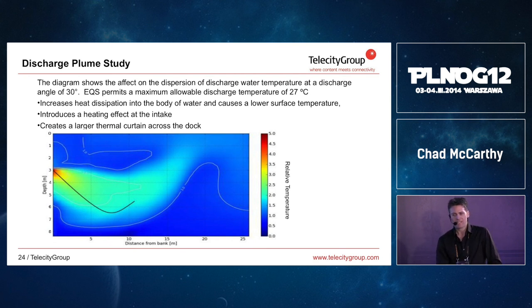This causes increased heat dissipation but lowers the surface temperature, and the surface temperature is actually where the exchange of heat takes place, so it's actually better to have a higher temperature at the surface and to protect the body of water underneath. What it also does is introduce a heating effect at the intake. So the red and the green is the discharge of the warm water, which is leaving the data center with the heat energy. We also have to have a supply connection. And we wanted to supply at a depth of 6 meters, if you remember from earlier on in the presentation.